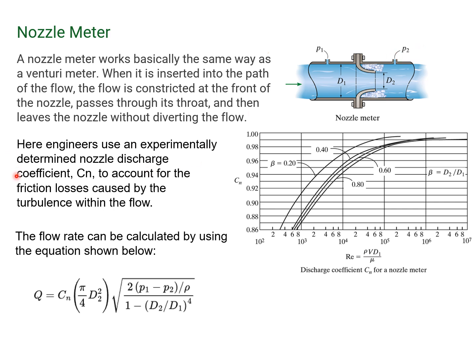Here, engineers use an experimentally determined nozzle discharge coefficient, CN, to account for the friction losses caused by the turbulence within the flow. Again, based on what Reynolds number you have, you come up and you come across and you get a CN value. This flow rate can be calculated using the equation shown below.